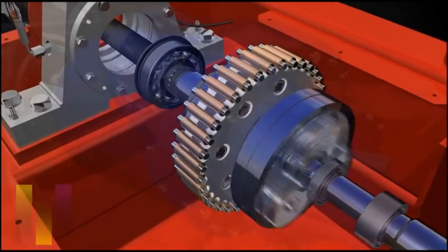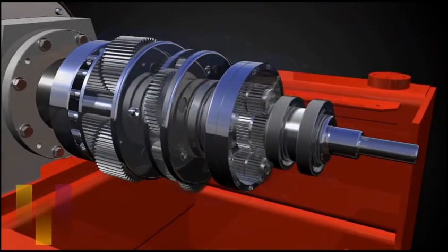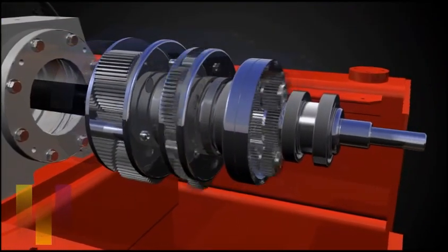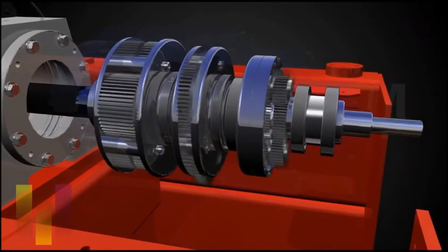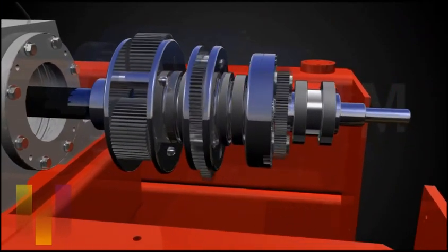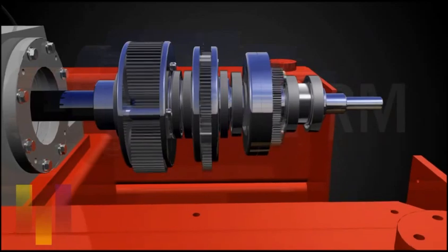If a gearbox is used, it is always an indirect drive system because the centrifuge conveyor shaft is not directly driven by the motor, but rather the sun shaft of the gearbox is driven and controlled via a VFD.